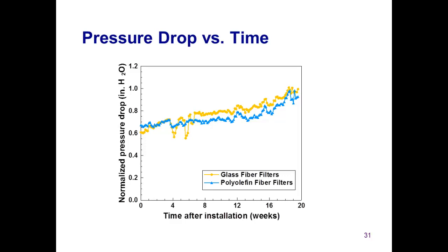As I indicated previously, a well-designed electret filter should have lower pressure drop than a non-electret filter for the same efficiency, or higher efficiency for the same pressure drop. Because the polyolefin filter in this study had the same initial efficiency rating and same pressure drop as the fiberglass filter, we can conclude that it is not a well-designed electret filter.